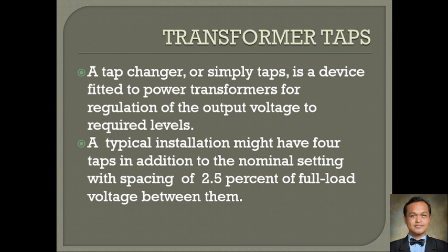These tap transformers are used on a power system or a line wherein the theoretical design was not met because maybe there's a little error in the actual, and you need to raise the voltage a little bit to compensate, maybe 2% or 5%.